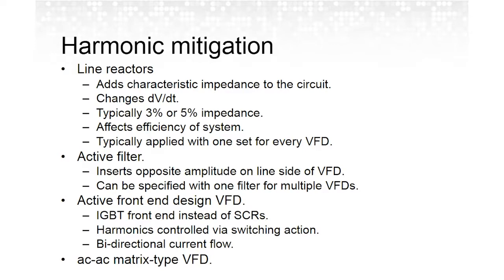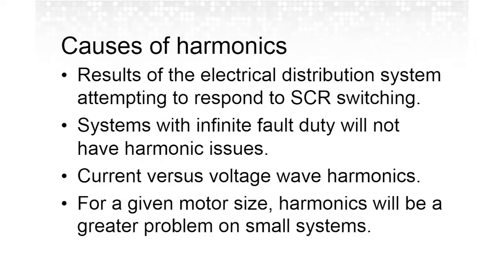Another way of harmonic mitigation is an active filter system. This is sort of similar to the active front-end VFD design philosophy, except it's in a separate enclosure. It basically inserts equal and opposite amplitude to the harmonics that you're creating with the VFD. The one benefit to this is that you can specify one filter for multiple VFDs, but just like an active front-end VFD, they are expensive. And then finally, AC to AC matrix type drives are another valid way to address harmonic mitigation, in addition to 12 pulse and 18 pulse transformers. So with that introduction to the bits and pieces that we use for harmonic mitigation, Ken will talk a little bit more about the cause of harmonics.